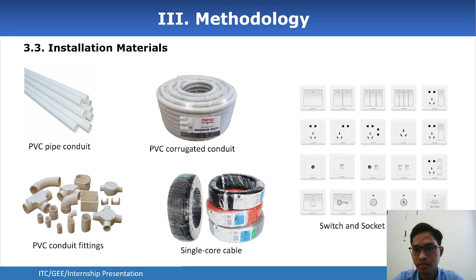For the PVC pipe installation, we divide into 2 sections. The first section is installation of PVC pipe inside the wall, and for this method we do 3 steps. The first step is wall chasing. We need to use the cutting motor to cut the wall surface to a depth of 50 millimeter or 5 centimeter. The next step is mounting on the wall. We mount the PVC pipe conduit at the place where the power socket and the switch will be placed. And after we place the PVC pipe, we cover it with cement plaster.